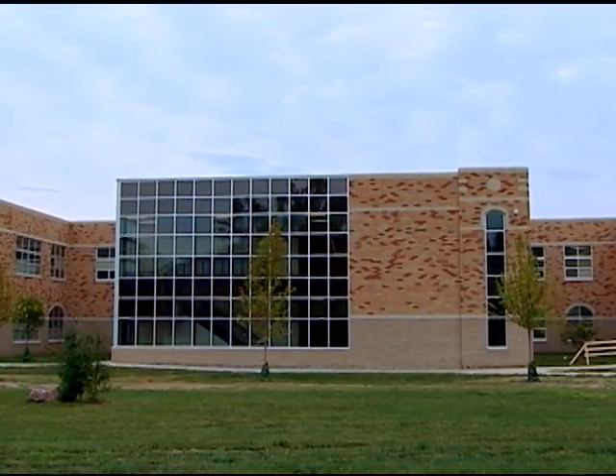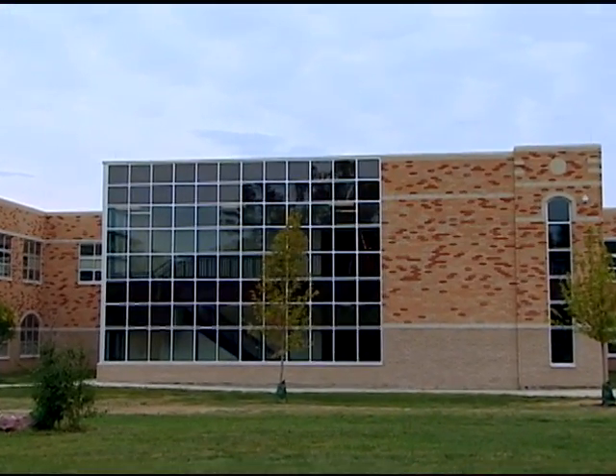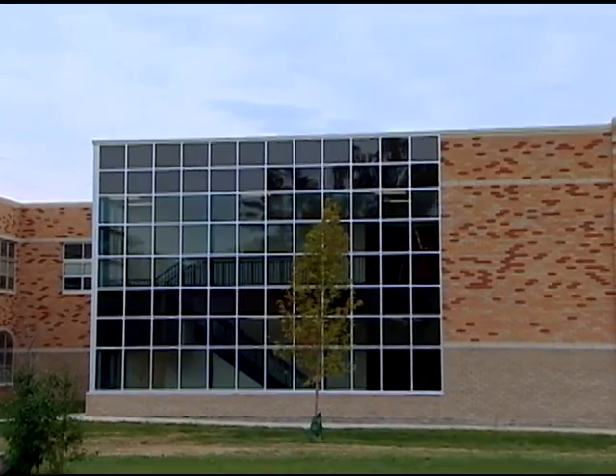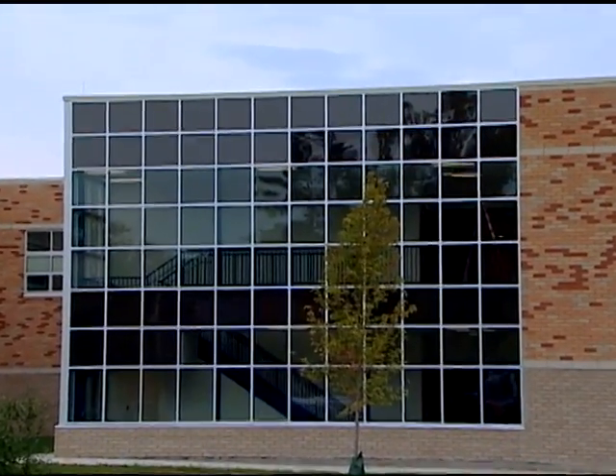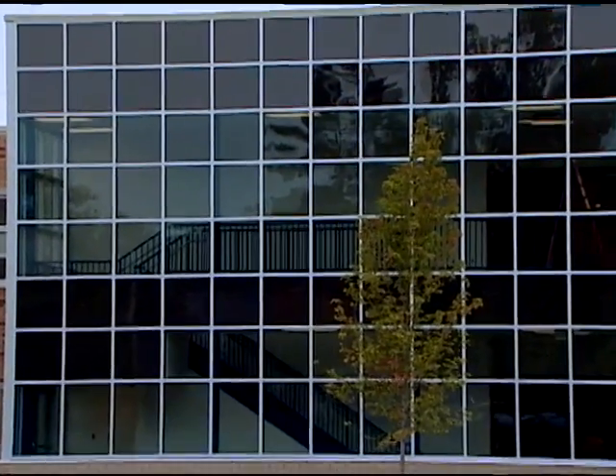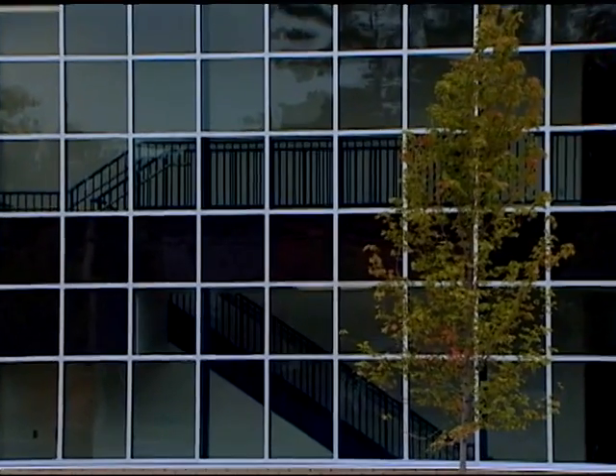This is east glass, which gains lots of heat. So the question is, are we creating a problem for the building, or wasting energy? The answer is a little bit, but one thing you may notice if you drive by is these windows have a tint on them, called a shading coefficient—about half the heat energy hitting these windows from outside isn't coming through. So there's a lot of filtration at this level, but also a lot of light coming in.